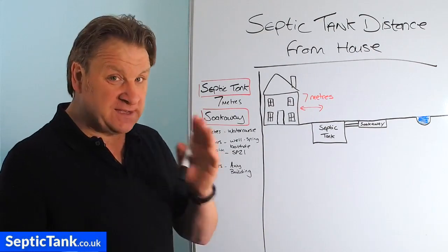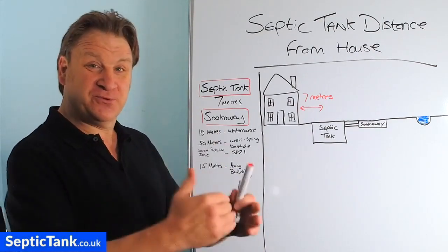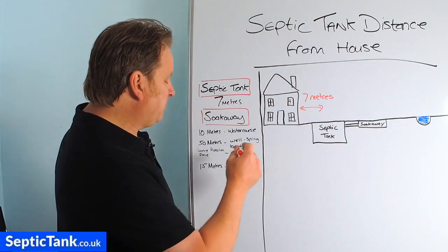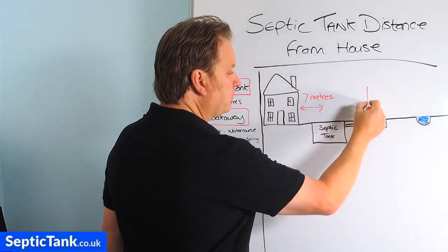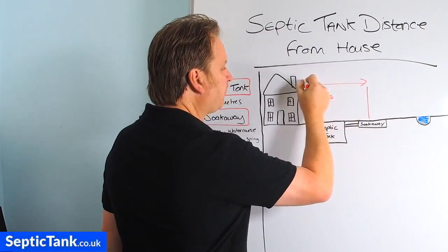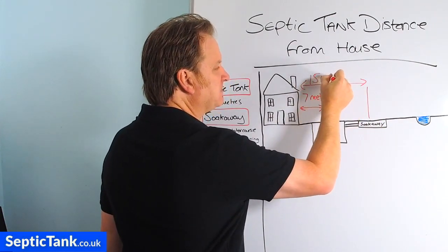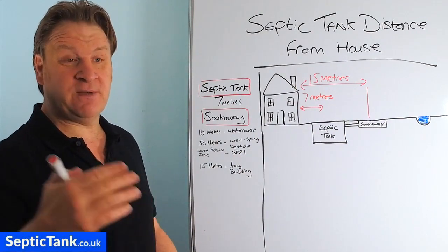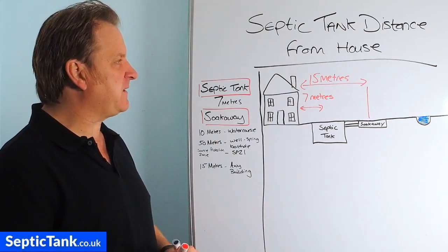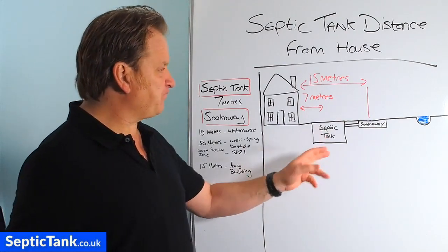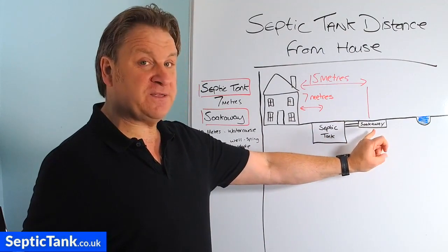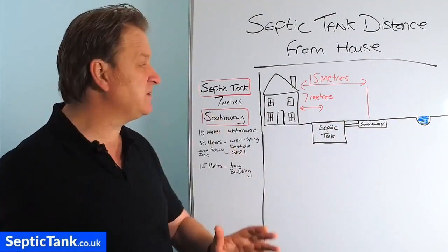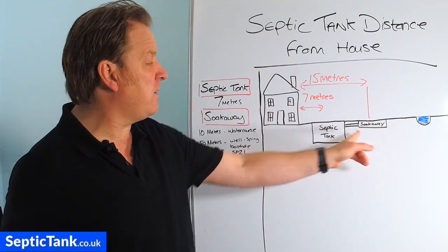So now what about the soakaway? Well, that's got a few more rules and regulations attached to it. How far does a soakaway need to be from a building? Building regs states that the soakaway needs to be at least 15 meters from any building, which is about 45 feet — whether that's your building, your neighbor's building, an outbuilding, anything like that. It doesn't really matter how far the soakaway is from the septic tank; we're only talking about how far the septic tank and soakaway are from any building.